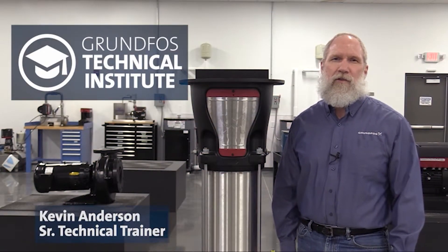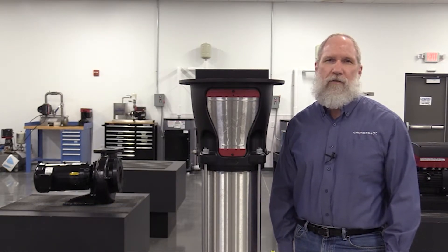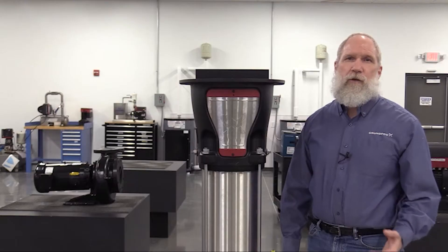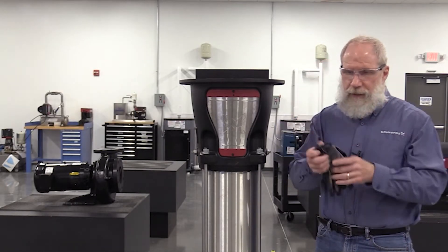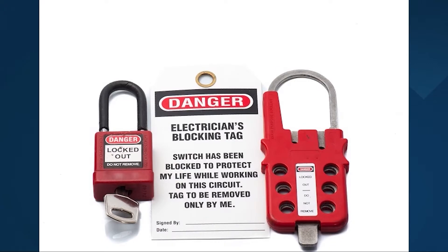Hello, in this video I'll demonstrate how to properly replace the cartridge shaft seal on our Grundfos CR models 95 to 255. The procedure for this process can be found in the Grundfos instructions CR CRN 95 to 255, 50 to 60 Hertz service instructions. Prior to doing any mechanical work on the pump, we recommend that you put on the needed PPE — personal protection equipment — and make sure that the pump is isolated and not under any pressure, and also make sure that you follow any needed safety precautions and the proper lockout and tagout procedures.